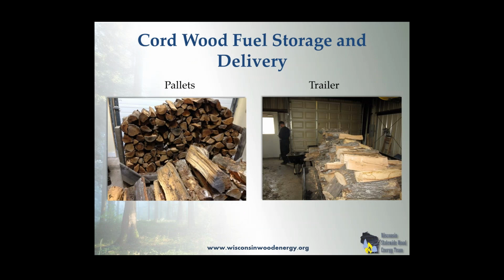These 2 projects, this one is done at Harvard on the left, and the one on the right is down in Missouri, a small school in Missouri. And they're both a little bit automated in the way they handle pallets, the cordwood. The one on the left, they have students that come up and work in the summer, and they load these pallets with, I think it's about a ton of wood on a pallet, and they store them that way for drying, and then they deliver them with a forklift. They have a load cell on a little hand cart, forklift hand cart, that tells them the weight of the fuel. They measure the moisture content, and they do that for some research purposes at Harvard. And they minimize the handling, because once it's stacked in these, they can move a ton of wood at a time, and it's delivered then directly into the boiler.